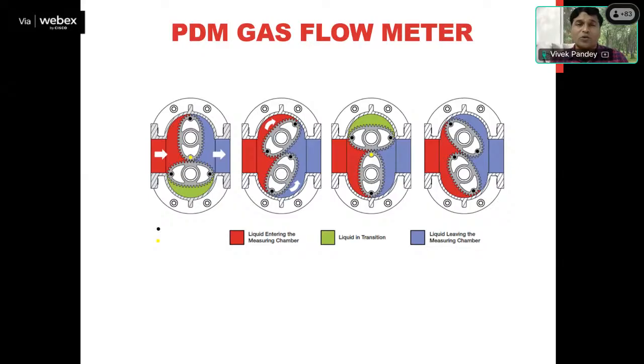So in one complete rotation of these oval shaped gears, because of the gas flow, obviously when the gas is flowing through the meter, it will apply pressure on these gears and the gears will rotate. Due to the change in the position of these gears, a certain quantity of gas will be trapped inside the cavity, and then it will pass through the outlet of this gas meter. So within one complete rotation, a certain amount of gas will be transmitted. So this is another technology being used for the measurement of the quantity of gas.